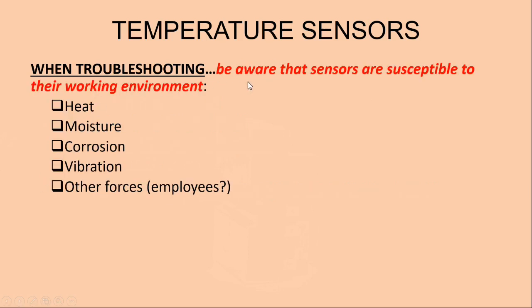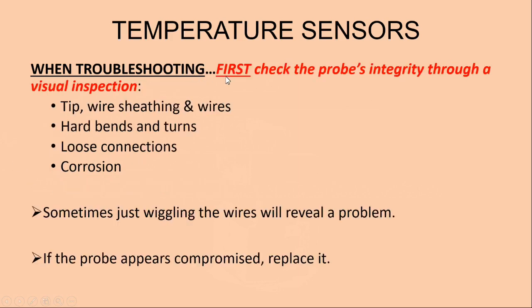When troubleshooting, be aware that sensors are susceptible to their working environment, so they can fail as a result of that, such as heat, moisture, corrosion, vibration, and other forces. When troubleshooting, first check the probe's integrity through a visual inspection. Check its tip, check the wire sheathing, check the wires, look for hard bends and turns, look for loose connections, look for corrosion. Sometimes just wiggling the wires will reveal a problem is with the probe. If the probe appears compromised, replace it.